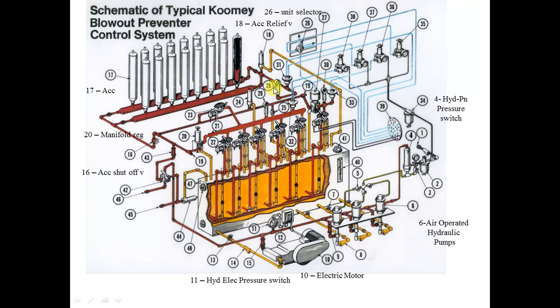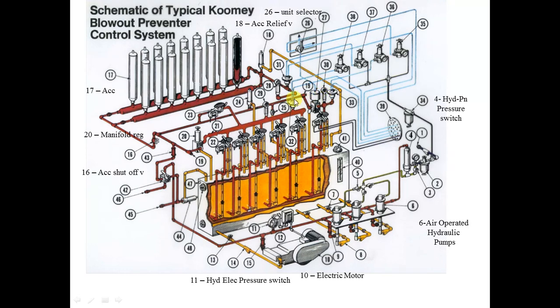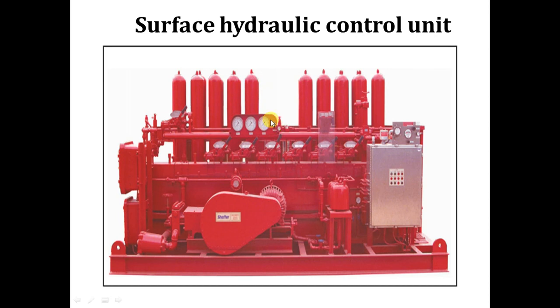Number twenty-eight is the accumulator pressure gauge — reads plus or minus 3000 psi. Number twenty-nine is the manifold pressure gauge — reads plus or minus 1500 psi. Number thirty is the annular pressure gauge — reads from 600 to 1500 psi. These three gauges may be separate or shown together as one instrument cluster on the panel.